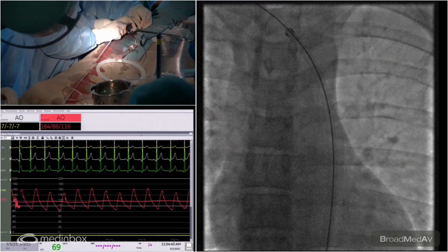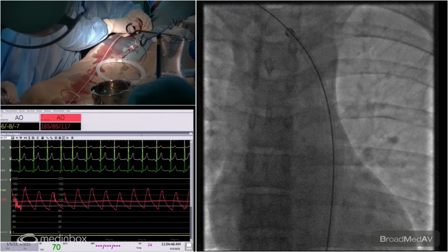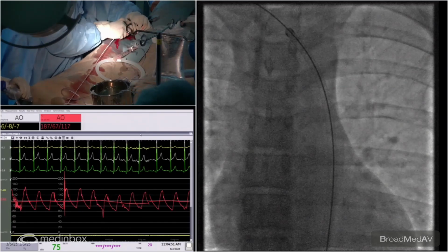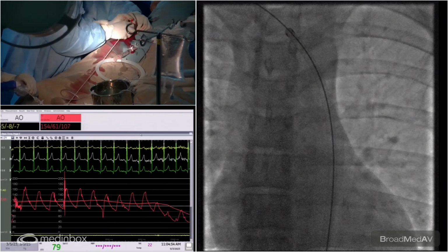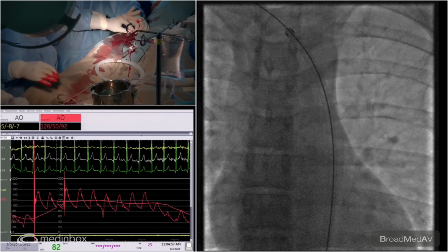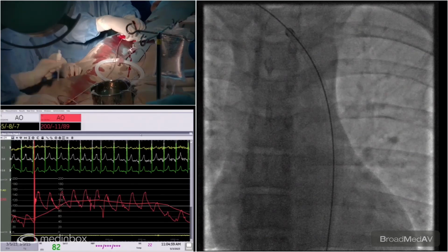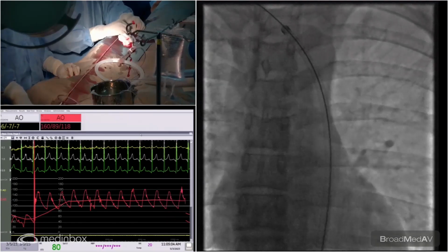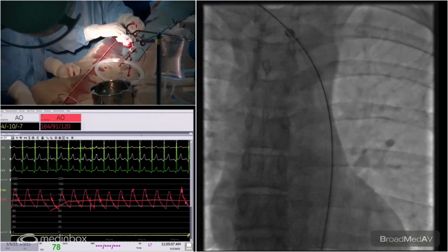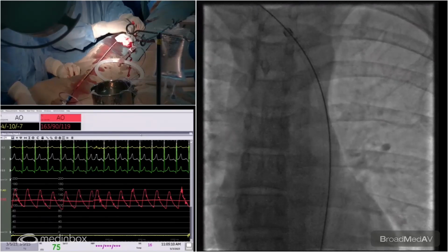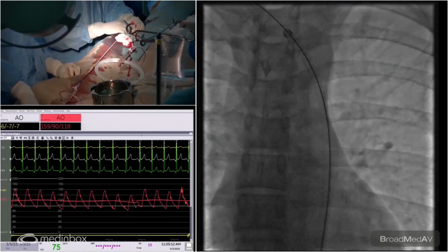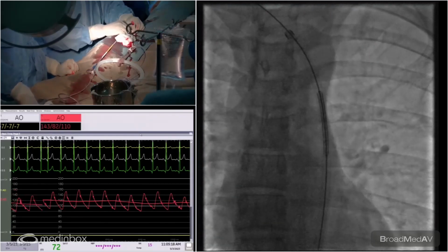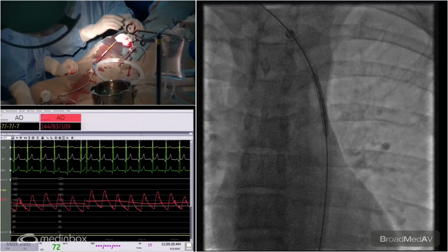The third type of stent is the Cheatham platinum stent, which is a platinum iridium stent, and that is also a closed cell stent, which too foreshortens. And then there are a group of hybrid stents. Hybrid stents are those stents that have a closed end, but the mid part is open cell. So it allows less foreshortening compared to a standard closed cell stent.